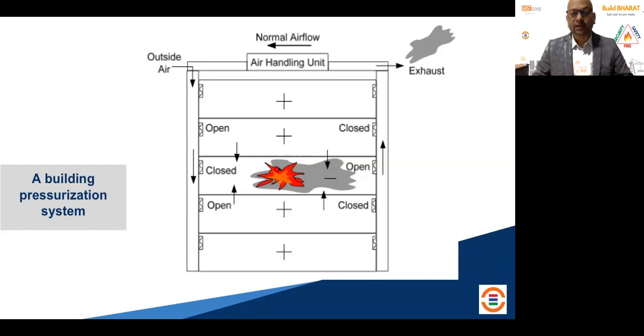If it is a server room, you must have heard that you need a fire rating of 2 hours to enclose that server room, because that's the most critical area, the more fire prone area. And in case a fire happens, if you have a civil wall which gives a 2 hour fire rating, the fire and smoke are contained there only. It doesn't go out for at least 2 hours. By that time, the fire tender can come, or you can fight the fire. 2 hours is a long period. So this is one way, passive.